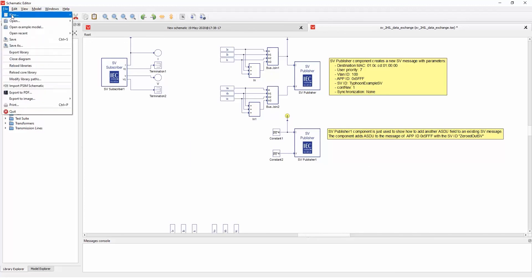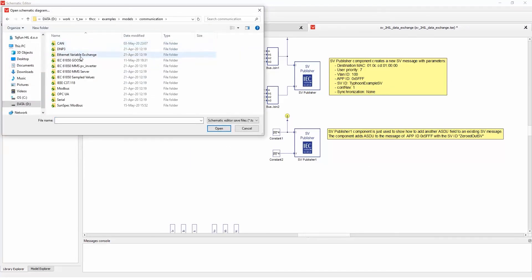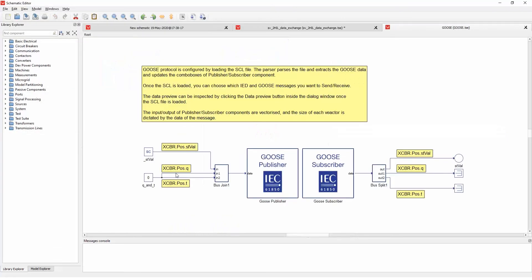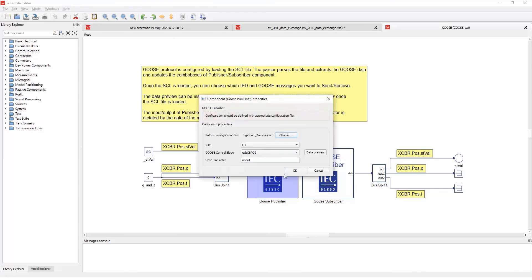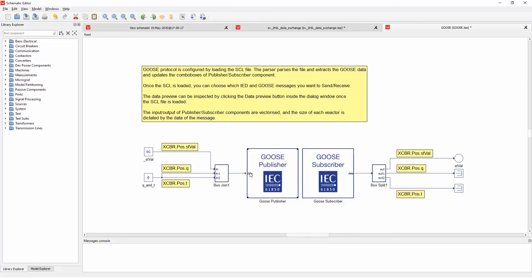Okay, going next to the Goose example. We can see it's a simple example, but you can see how everything is configured. Inside, we have the SCD file loaded, selected control block, and in the subscriber does exactly the same file, and data set is selected to subscribe to. And because there is only one terminal, it must be a vector signal, and here we use bus join to join the values and here to split the values using bus split.